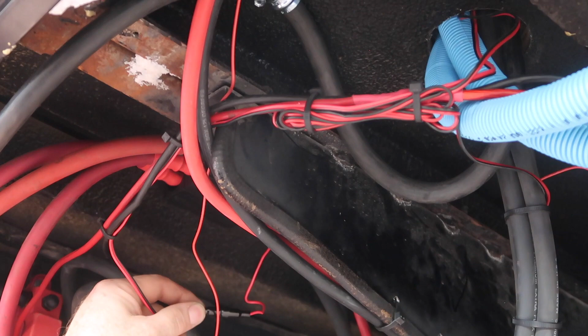There's some big breakers up there - I believe this is a 100 amp breaker, and this is for the solar charge controller. These are actually fuses, not breakers - a 100 amp fuse, and then 150 amp fuses for the two inverters, so the inverters are fused at this point. This last block here is unused, no fuse in it - that's for future expansion. We had 4 fuse holders, so we put them in.